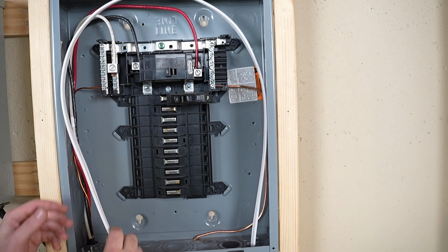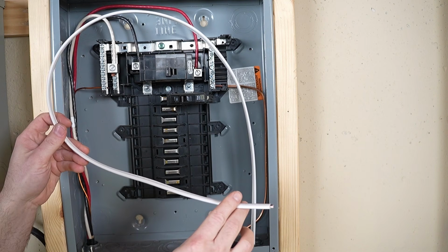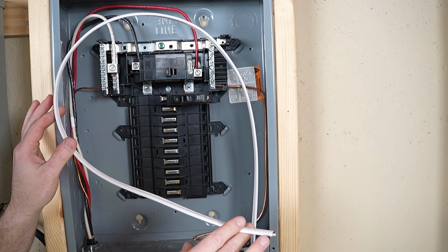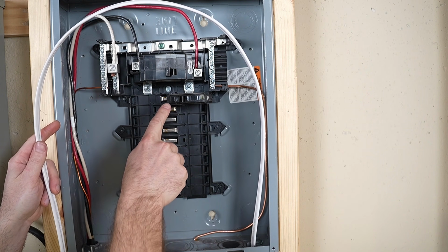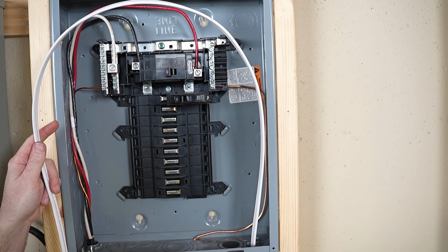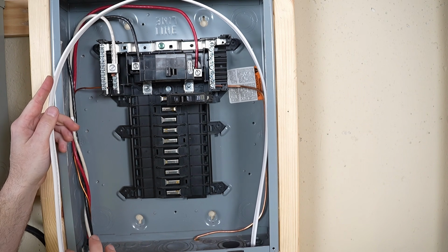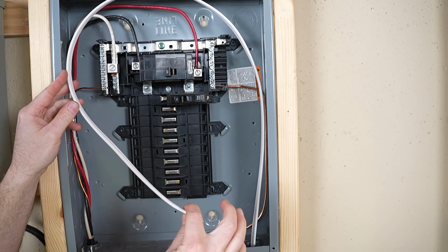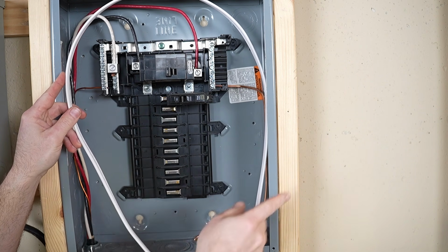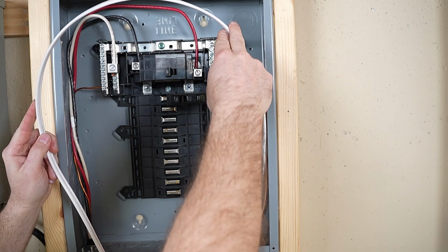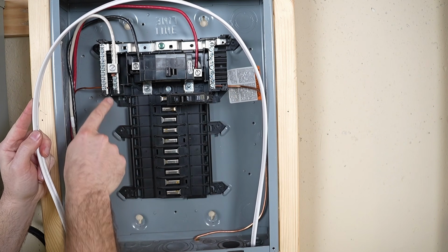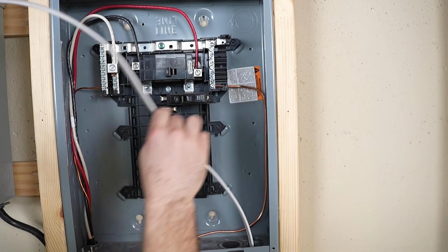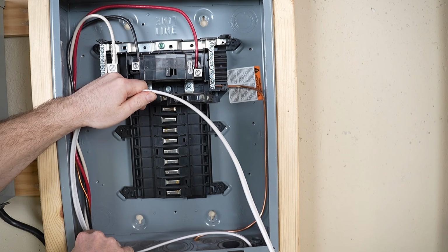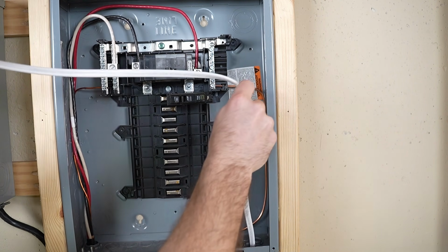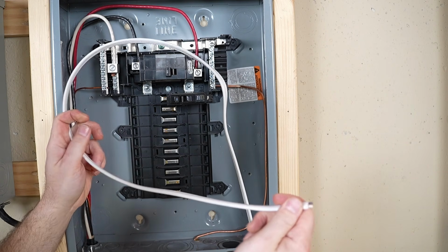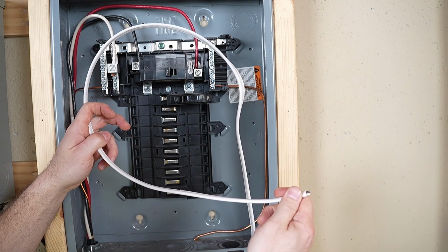So now we've got a target for where our wire is going to land. Remember, we left ourselves plenty of wire here, and a lot of people look at this as waste. It's not waste, it's cheap insurance. In this case, we put our circuit breaker right here, everything worked out very well. But if something were to come up during the installation, let's say we've already ran this wire, and we were gonna plan on putting it here, so we only cut it this long. Well, what if something comes up and now the circuit breaker needs to be over here? We would actually have to have quite a bit more wire to reach that location. Always leave yourselves options. Don't look at this as waste, look at this as options.